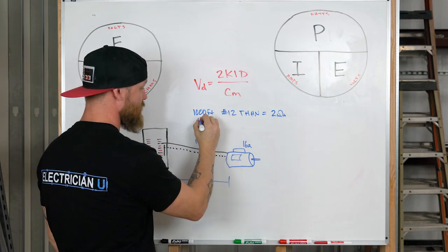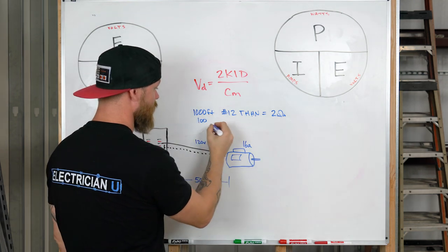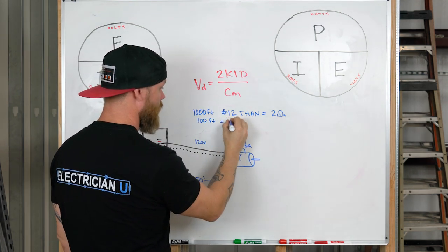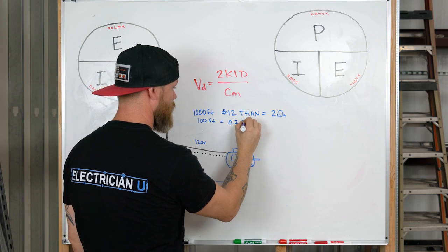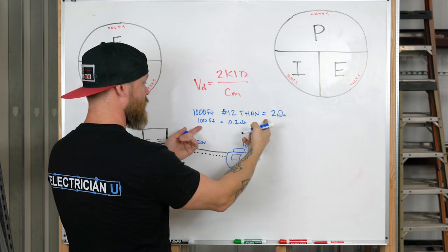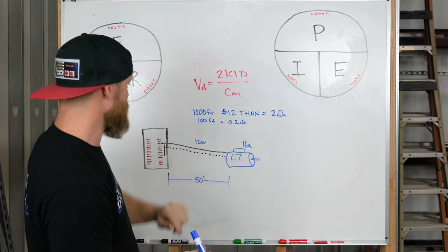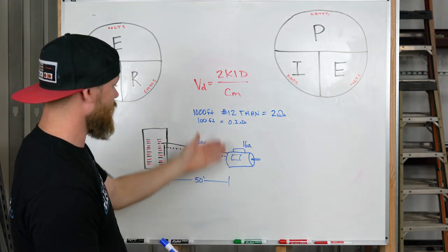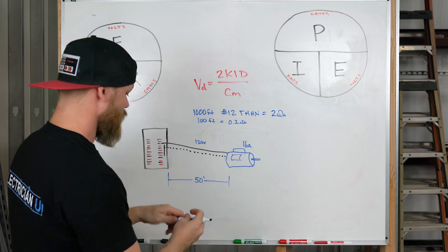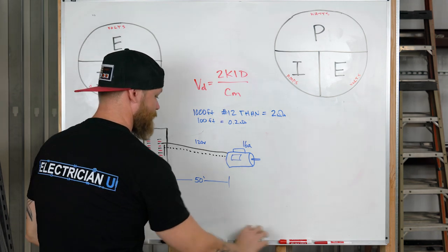So I can just deduce that if 1,000 feet is 2 ohms, well then 100 feet is 0.2 ohms. You just move the decimal place over one. So I know what my resistance value is now. I've got 0.2 ohms of resistance. I've got a 120 volt circuit, 16 amps.